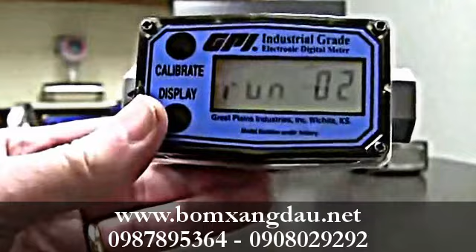But then again, most people are going to have a pump that goes the same speed, so one calibration is plenty because it's always going to be at that one rate. So in this case, I'm not going to do another run. I'm just going to go ahead and hold down both buttons. I'm not going to let go until it says cal end. Once that's done, I'm done. So now this has got a new calibration in it, and as long as I leave it on that calibration, it will read at that new calibration.